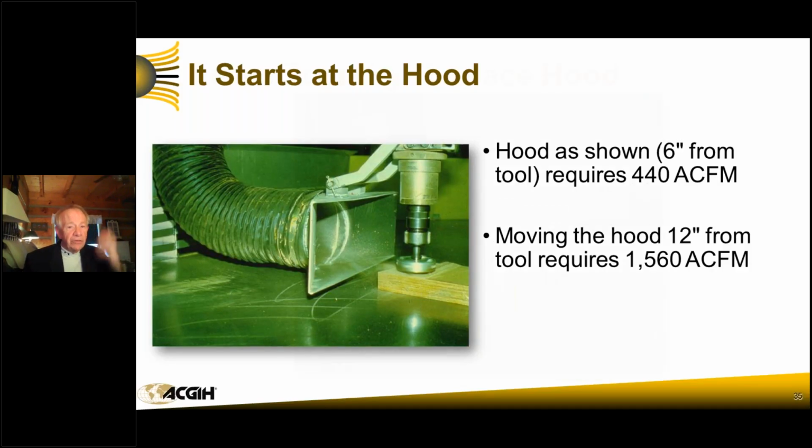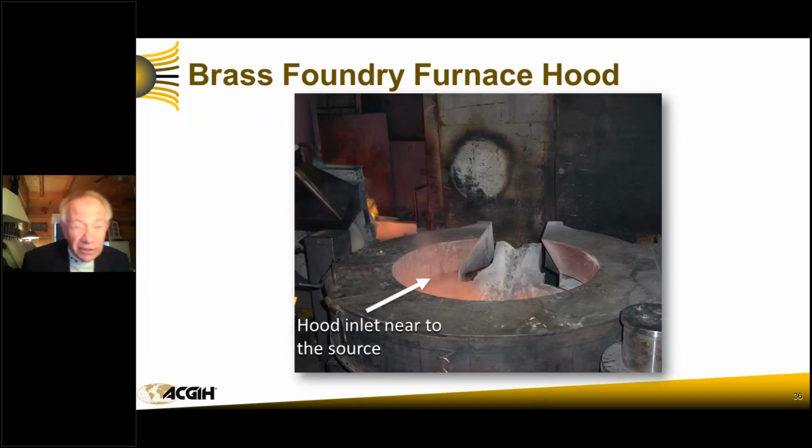This is in Rutherfordton, North Carolina. This is a brass foundry, and this is a furnace hood. You take the scraps after you pour the brass, and you end up with stems and a lot of pieces of flashing of brass that you want to return to the brass ladle. So what they want is an open top. So they have to have an open top in order to put the scrap back into it. So you've got to have it open.